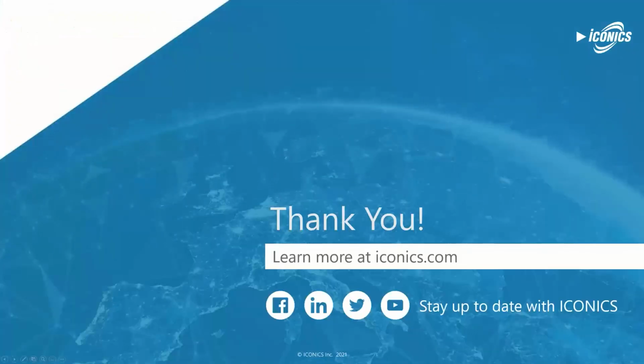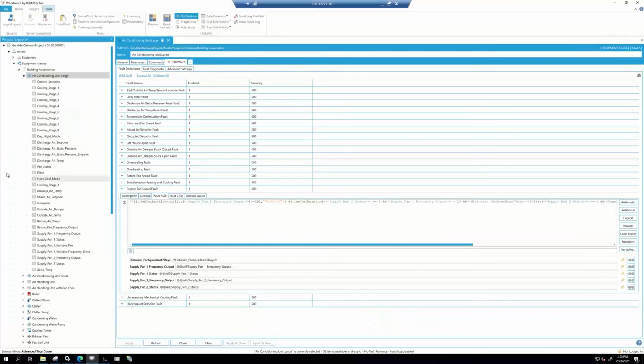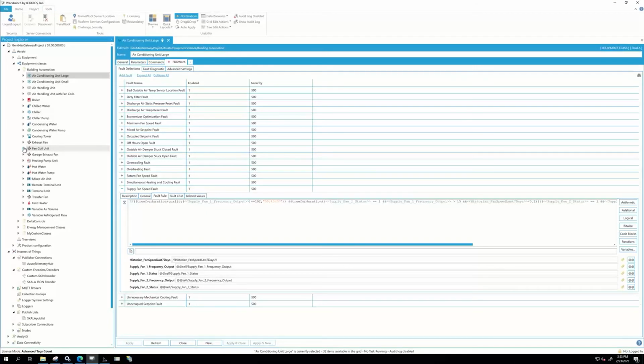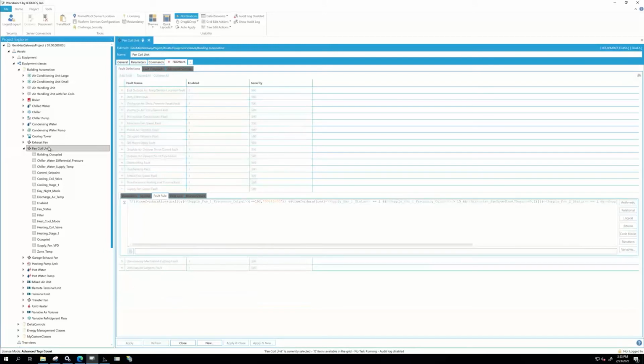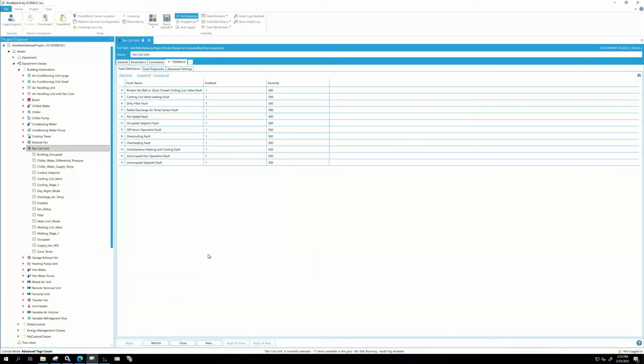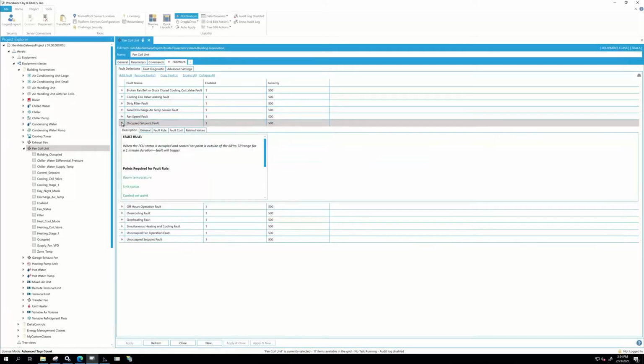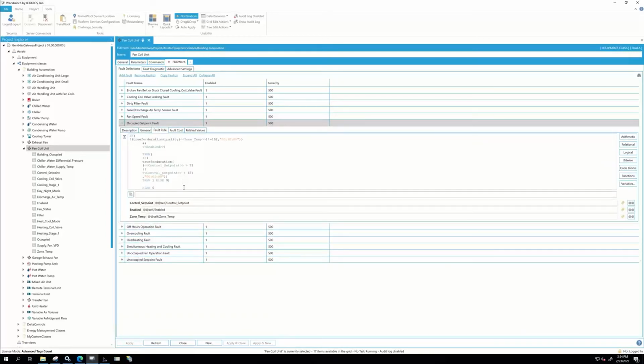That's nice to see, I'm glad you showed an example from your fault library. So do you roll out the fault library as a complete list of faults to every site, or do customers pick and choose the faults they want? In general, people use this as examples and pick and choose, because everyone's going to have a slightly different way of defining the fault. So this tends to be a template that people modify rather than just apply, because every manufacturer's fan coil unit is going to be different, and some will expose this variable or point, others won't. So it's very much a template, but it gives you a great start, in this case for buildings.